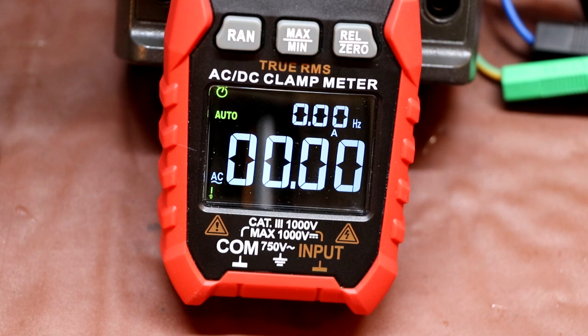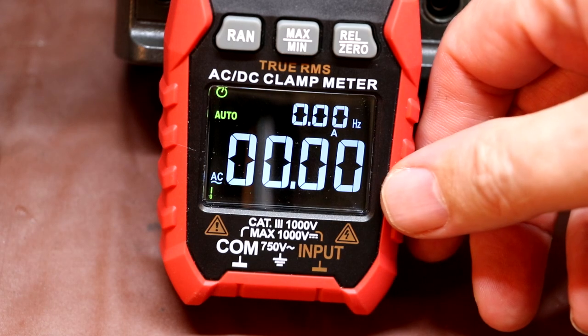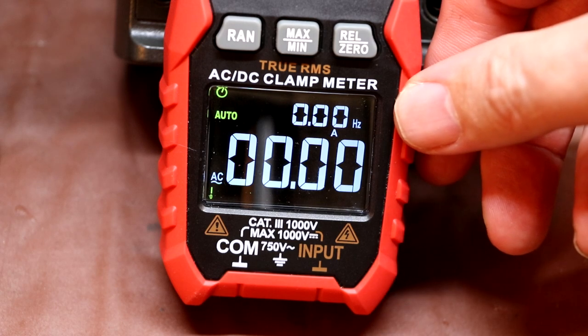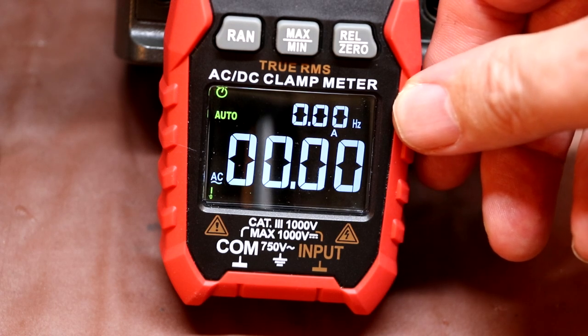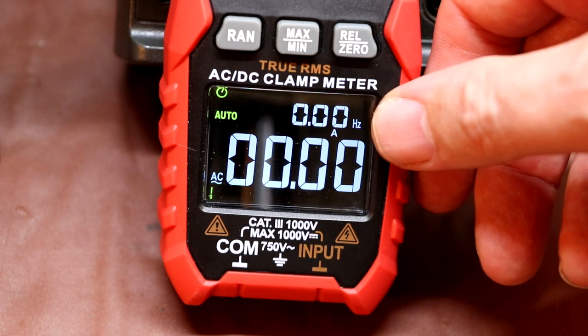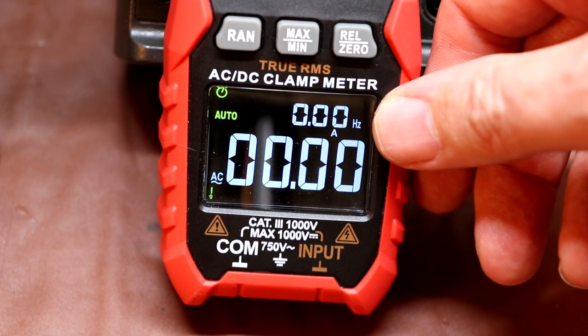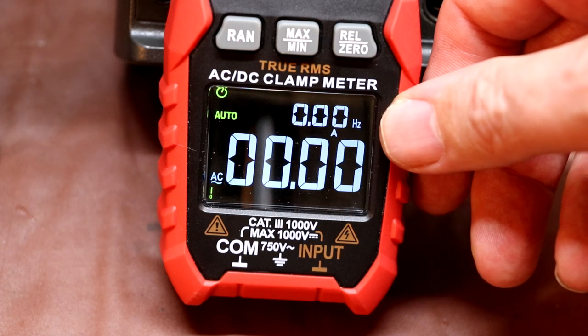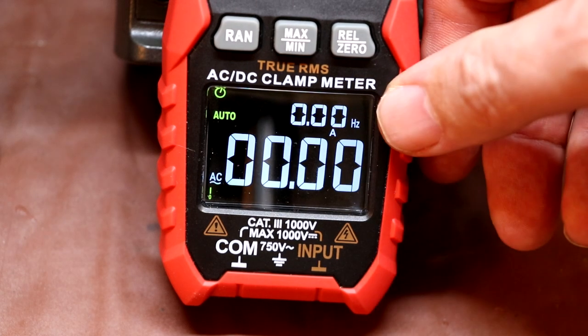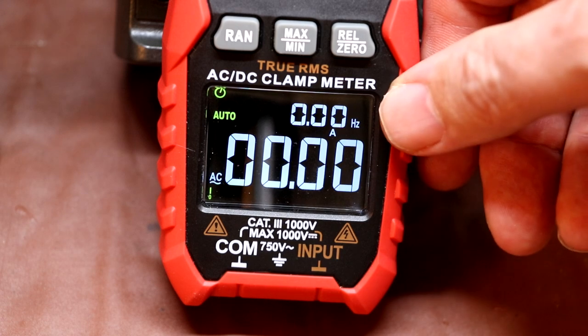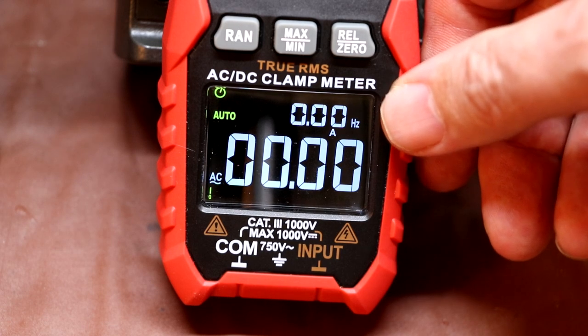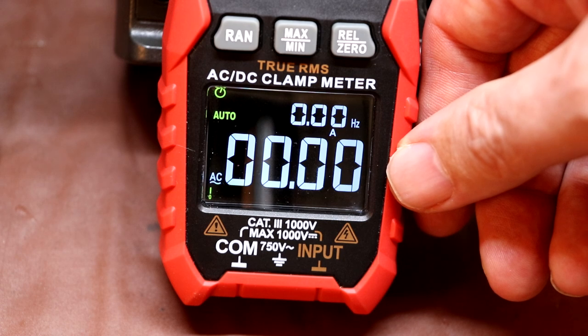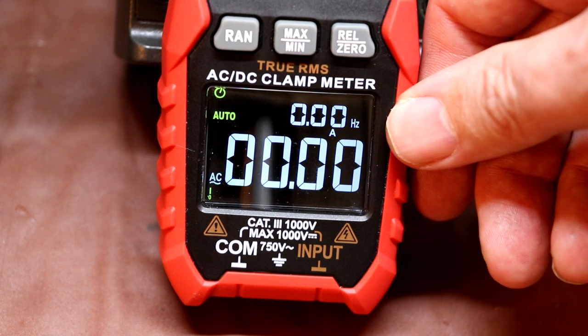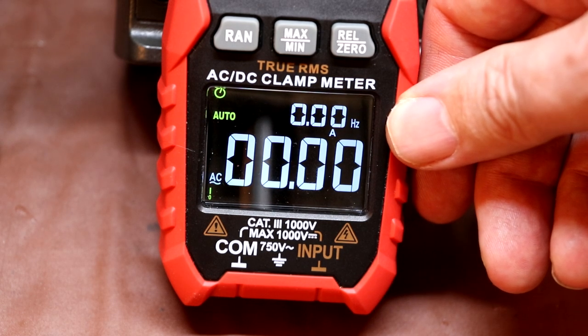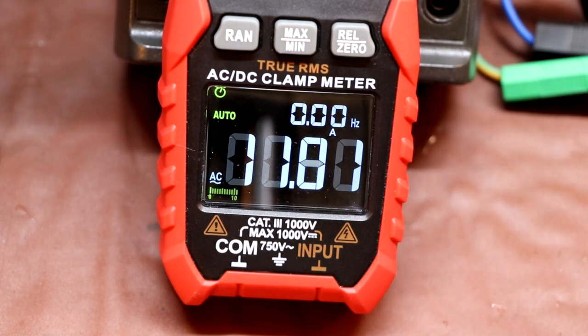Previously, when I was using the meter in the AC current range, I noticed that although it was measuring the current correctly, it also has a frequency display here in Hertz, but for whatever reason that frequency display always remained at 0, and I actually assumed that that was some kind of a fault or a bug. But according to the meter's specification the frequency indication won't operate until we're actually measuring a current above 25 amps. But let's go ahead, wind the current up, and we'll find out at what point it starts working.